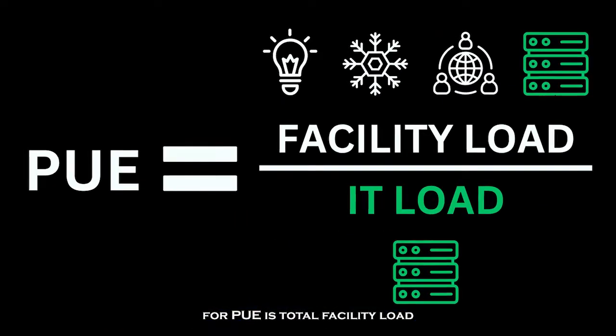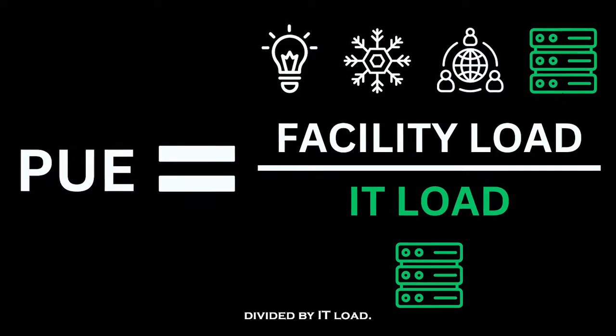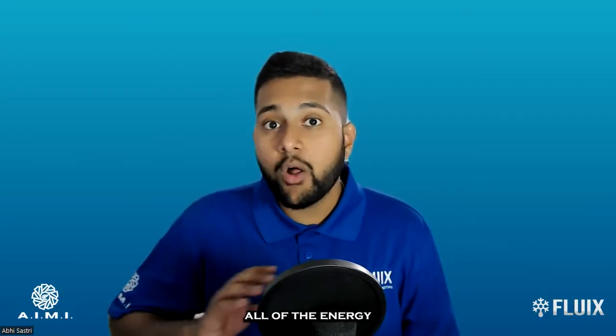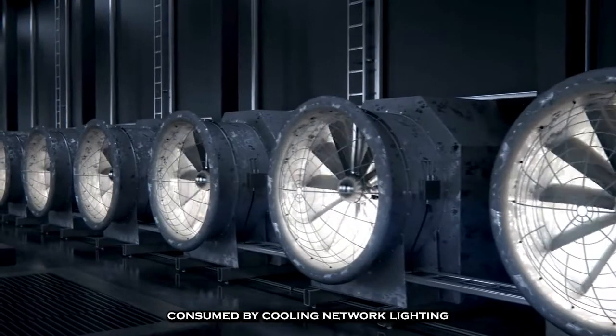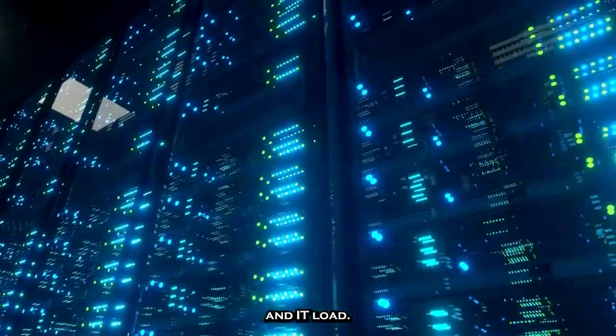The mathematical formula for PUE is total facility load divided by IT load. Total facility load includes all of the energy consumed by cooling, network, lighting, and IT load.